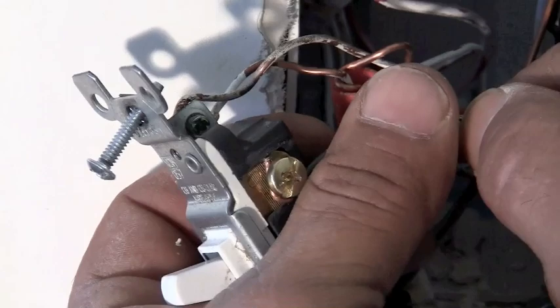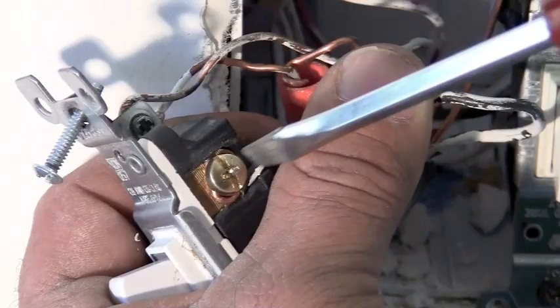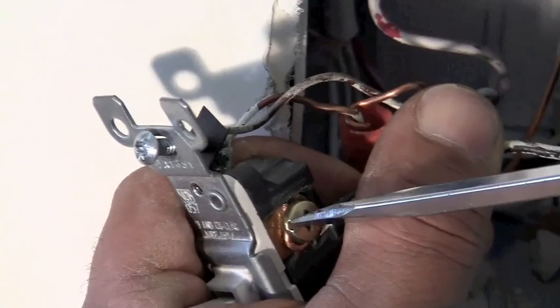Now when you tighten the screw, it's going in the direction of that bend so what's going to happen with that screw, the wire is going to pull around if anything and make it real nice and tight, otherwise it can actually pop out on you. It may not pop out right away but it can definitely pop out as you're putting that switch in the wall. Get it nice and snug tight and that is it.